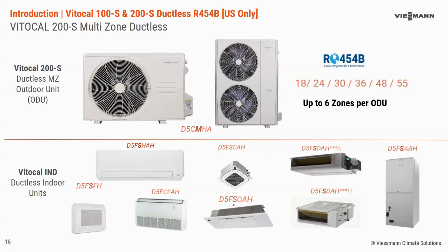So we talked about the 1-to-1, the single zone systems, if you will. So if you have the requirement for multiple zones off of one outdoor unit, that's when you're going to step up to the 200S, the multi-zone. So same concept of an outdoor unit pairing with an indoor unit, the difference being that the outdoor unit has multiple connection points for up to 6 zones per outdoor unit. So we have 18,000 up to 55,000 BTU available on these multi-zone.